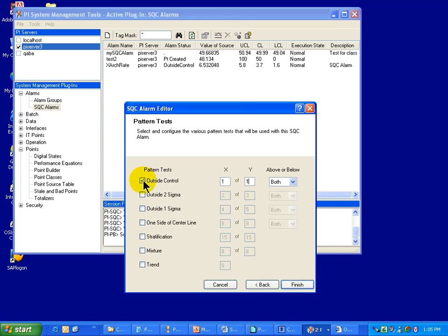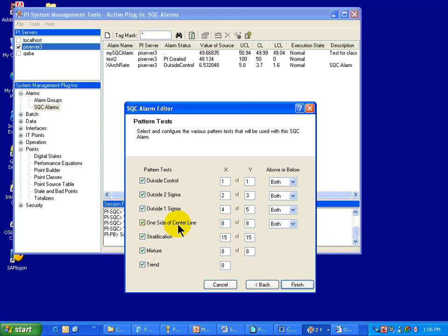We suggest you start with the outside control because it is the standard alarm that you hear about with statistical quality control — it's easy to explain and it gives a very valuable alarm to operations. These other ones are all standard and have their own purpose, but we would suggest turning these off and just using the first one because, when you roll this out in operations, you don't want a great number of alarms that are just confusing to people.